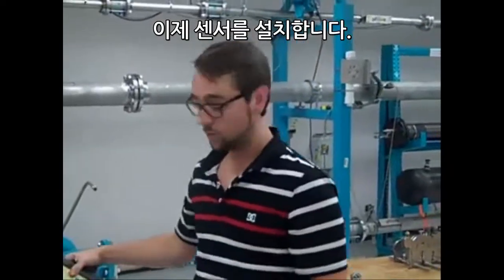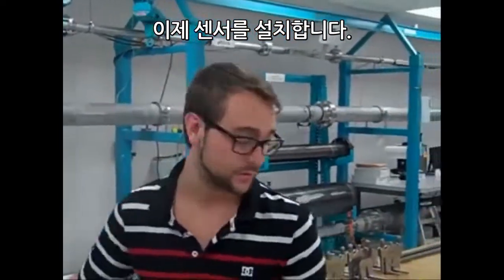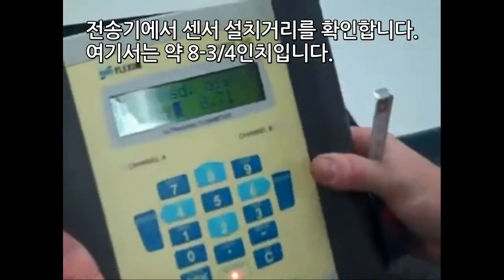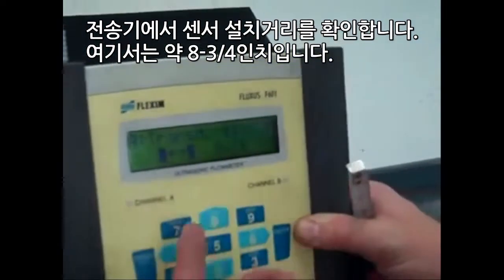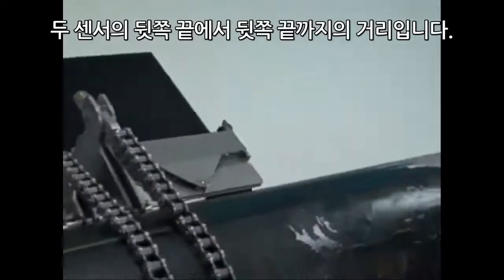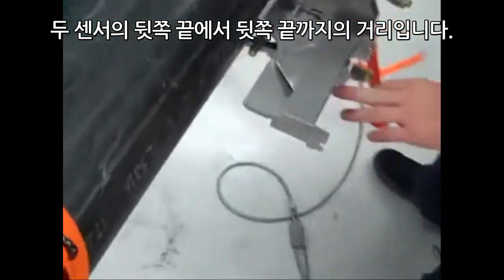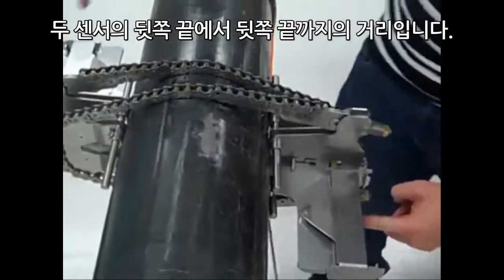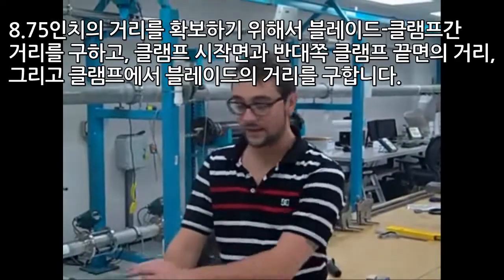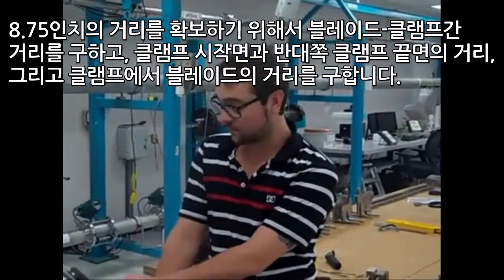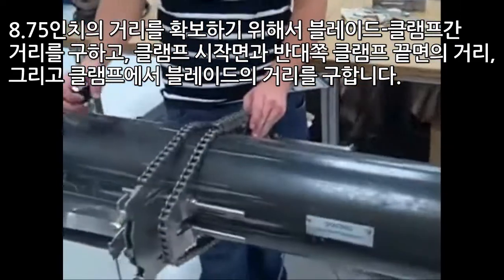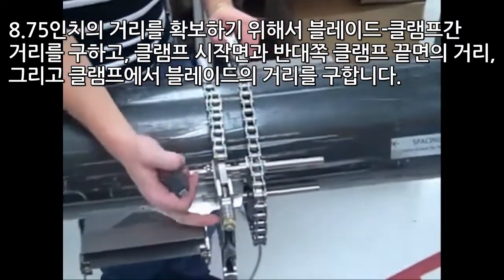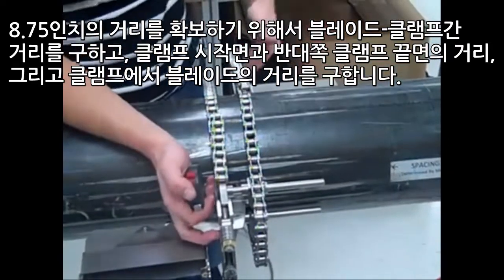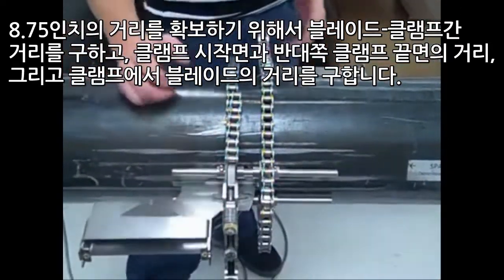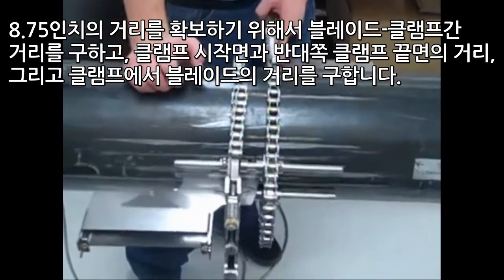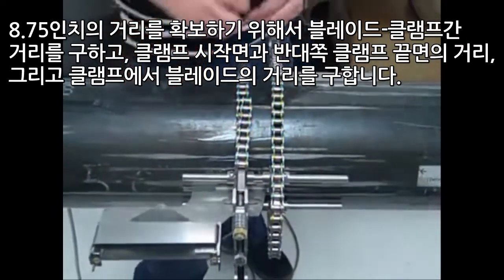Okay. Next step is to mount and install your transducers. Your meter has given you a transducer distance of approximately 8 and 3/4 inches. So that means you're going to go from tip to tail, from transducer to transducer. Okay. To get to 8.75 inches for your transducer distance, you're going to measure from the blade to the clamp's leading edge to the opposite side clamp's ending edge, and then from the ending edge to the blade. That comes to about 4.5 inches.